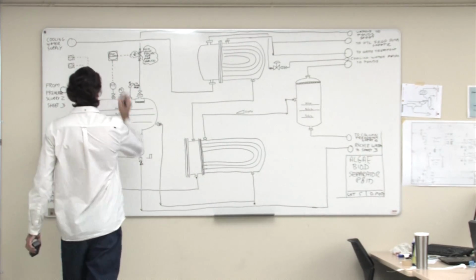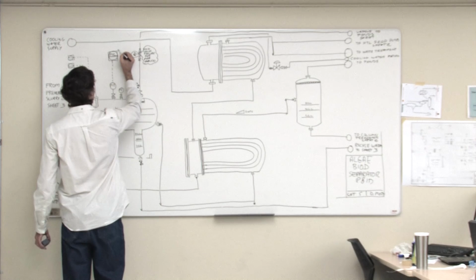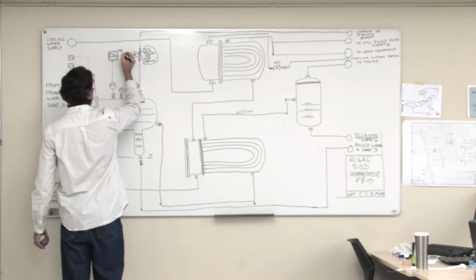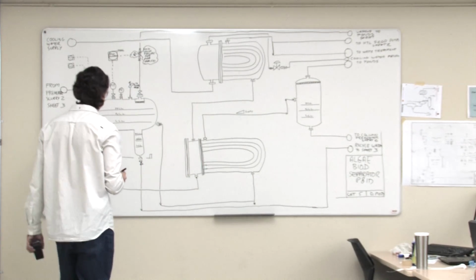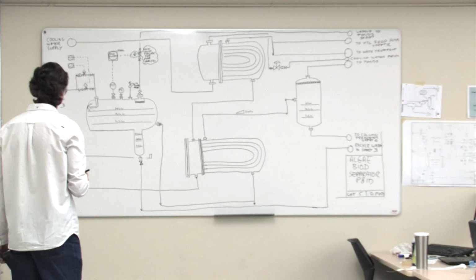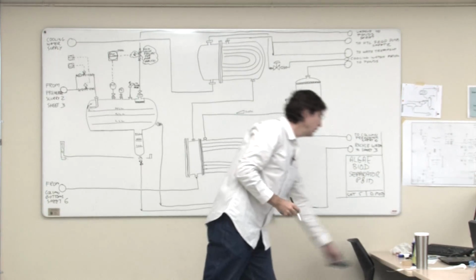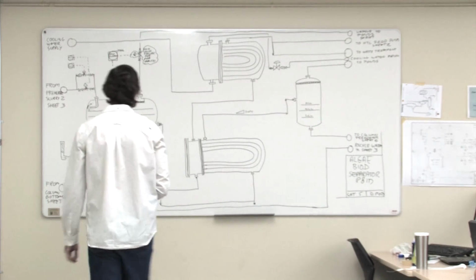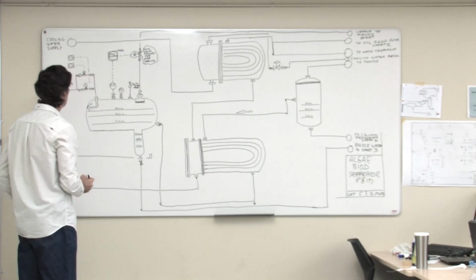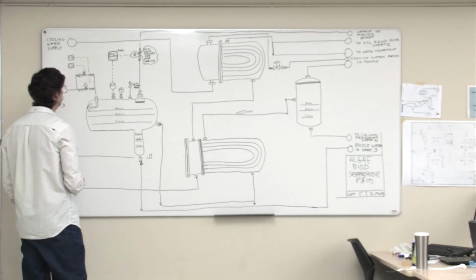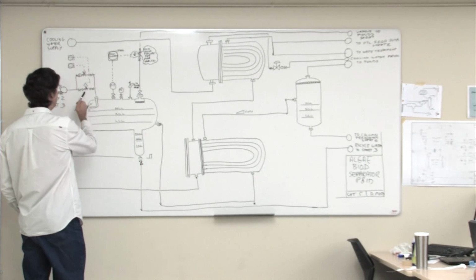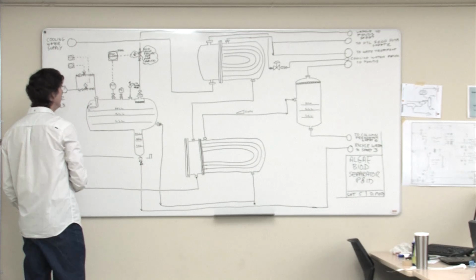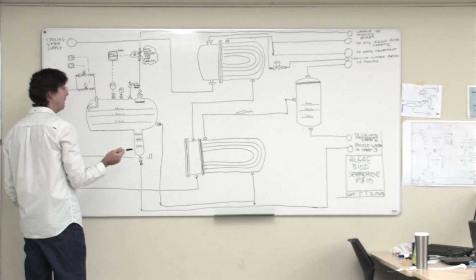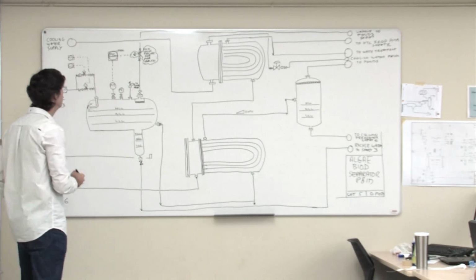We want to have a pressure alarm high and probably a low, like that. Do we need any interlocks on the pressure? What would we do if we found the pressure started to get high on us? It might be because this valve is sticking, and there's not much we could really do about it. We could shut the pumps down that are way upstream.